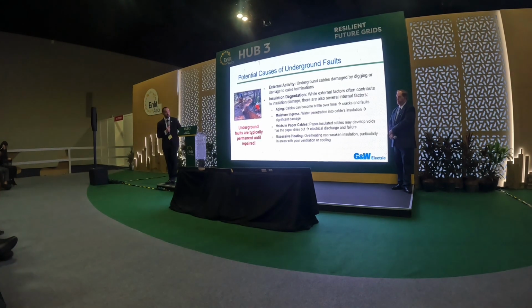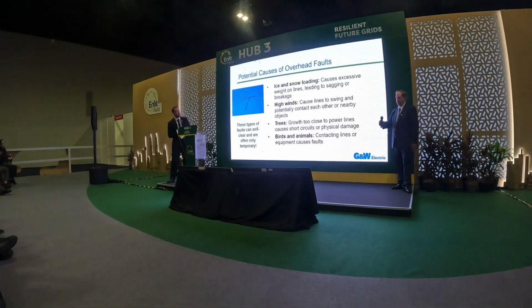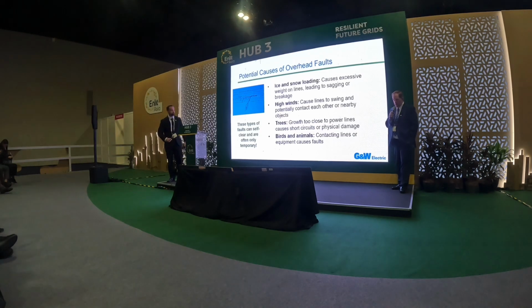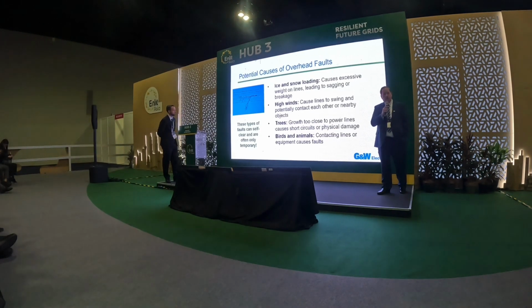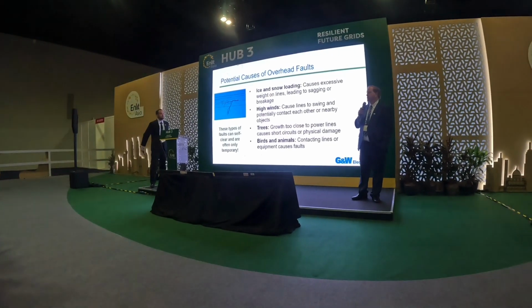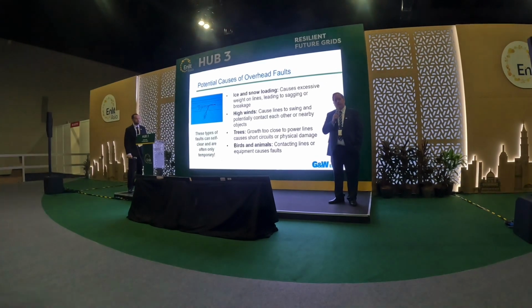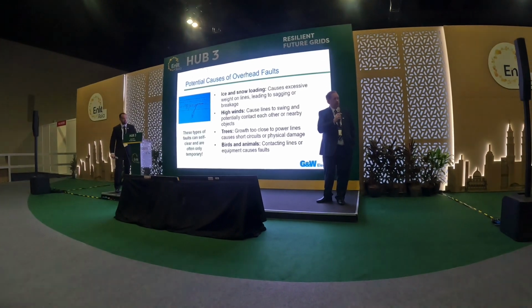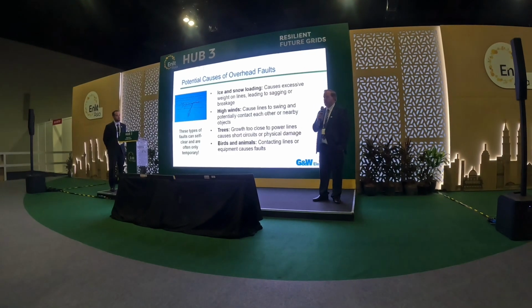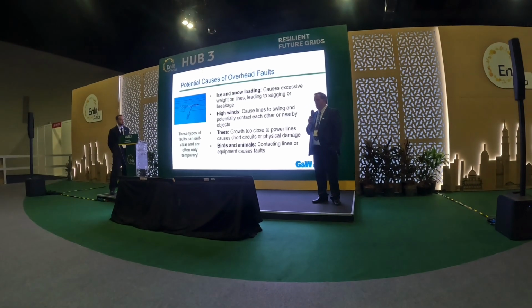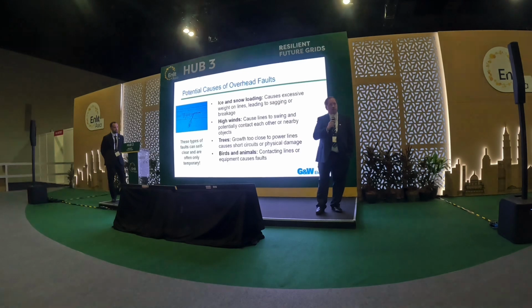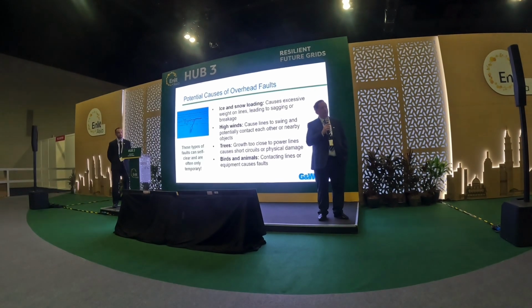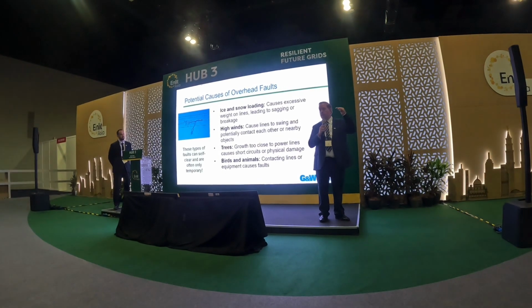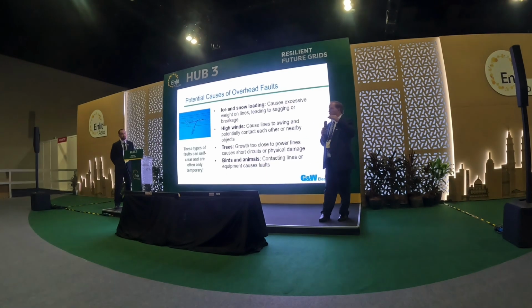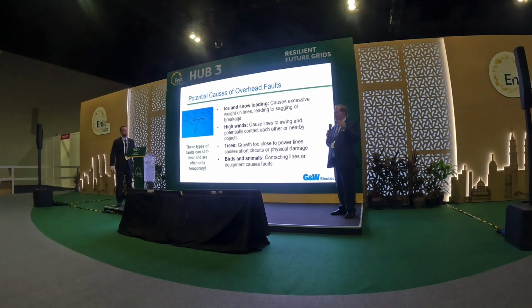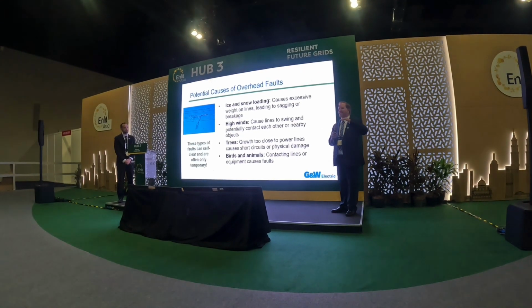So I'm going to transition over to Ron, who's going to talk a little bit about overhead faults. So as Kyle mentioned, when you have overhead, there are many situations that can occur. Unlike on the underground, when you have an overhead fault, it could be that that fault will self-clear. In fact, some studies have been done, and in some studies it's indicated that with automatic reclosing on these overhead lines, you can actually see up to 95% of these faults self-clear.